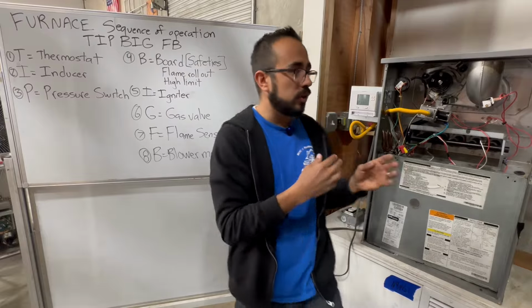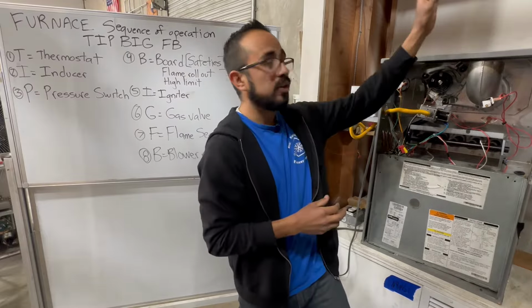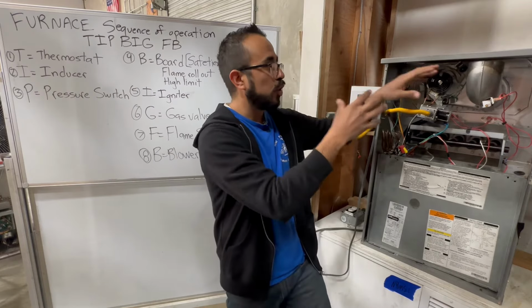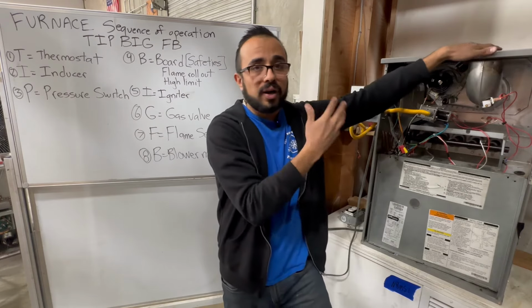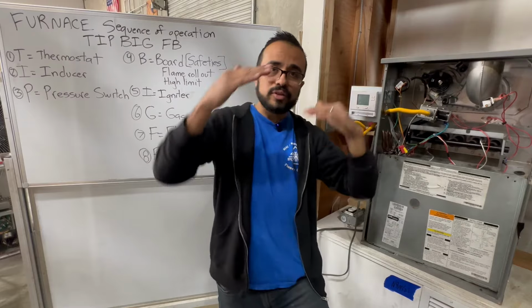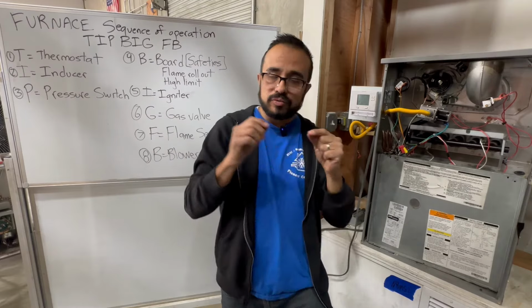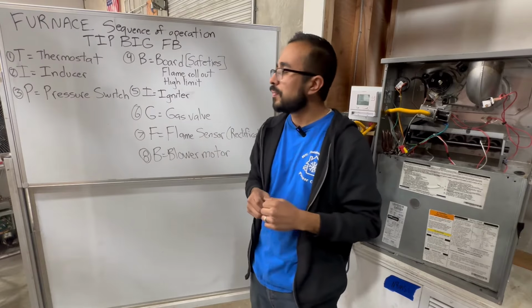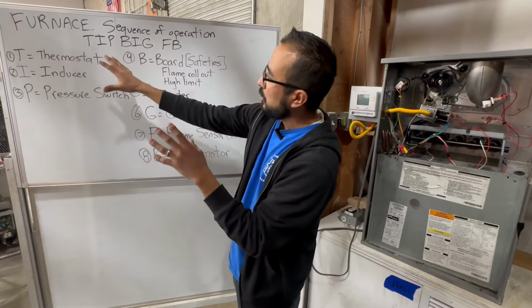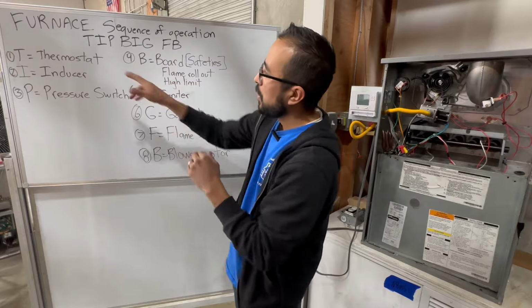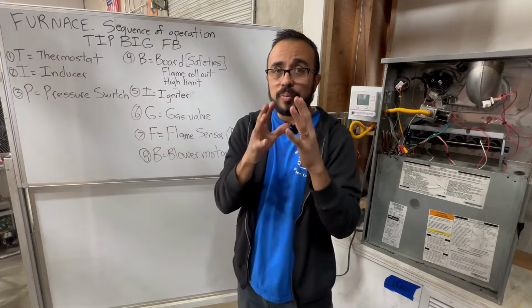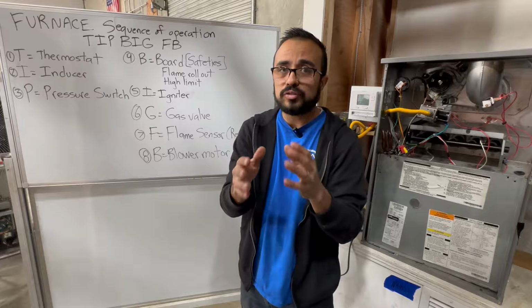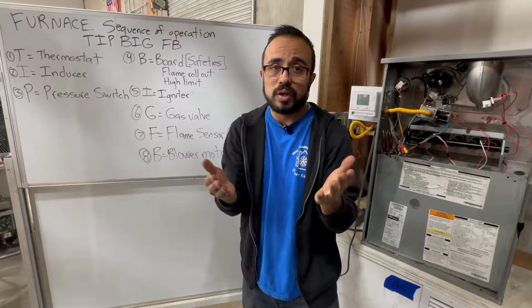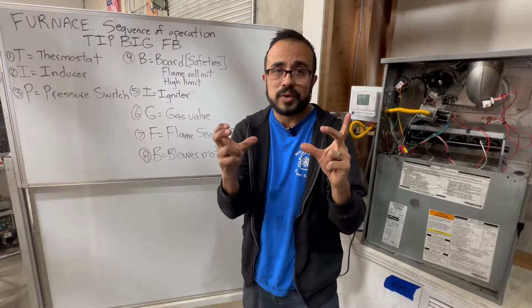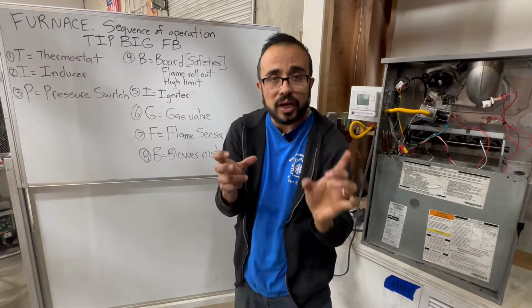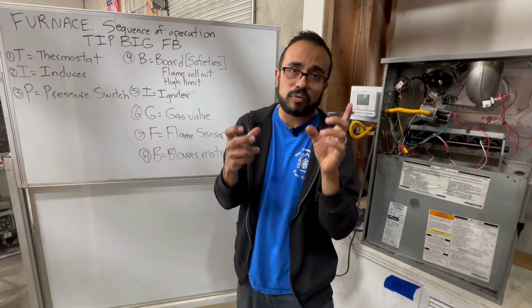Now, of course, this furnace here, I disconnected the flue, the vent, just to show you what a blockage would do. But a lot of the times you're up in an attic, horizontal, you don't have a lot of space, but just following these steps can help you with that. Now, going back to this, just doing a quick recap. The thermostat, the R, your power, sends 24 volts to W, right? So you want to make sure you're getting 24 volts between your common and your W. That's going to ensure that your W actually has 24 volts, that there's a call for heating.